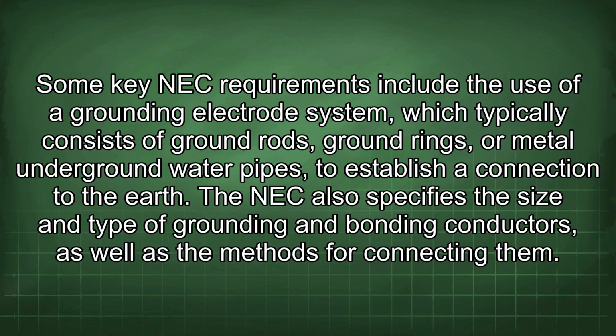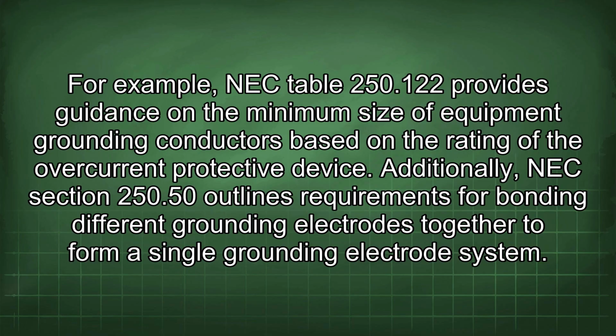Some key NEC requirements include the use of a grounding electrode system, which typically consists of ground rods, ground rings, or metal underground water pipes to establish a connection to the earth. The NEC also specifies the size and type of grounding and bonding conductors, as well as the methods for connecting them. For example, NEC Table 250.122 provides guidance on the minimum size of equipment grounding conductors based on the rating of the overcurrent protective device. Additionally, NEC Section 250.50 outlines requirements for bonding different grounding electrodes together to form a single grounding electrode system.